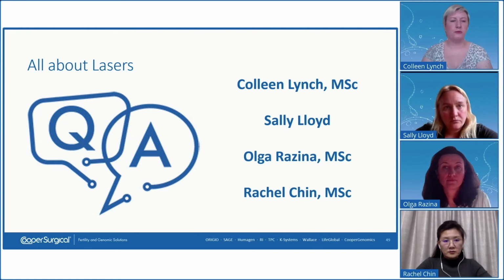Okay, so basically, the only check that the user needs to be doing then is the alignment. Is that correct? Yeah. Sorry, that was to do with the laser energy. Right. The alignment should be done every single day that you use the laser. In the case of the Saturn laser, turn on that pilot laser, check it's in the right position. It takes about 10 seconds, that's all.